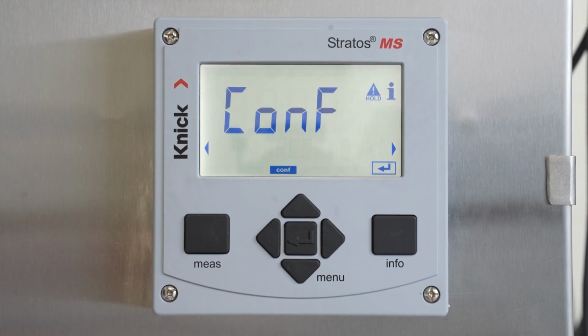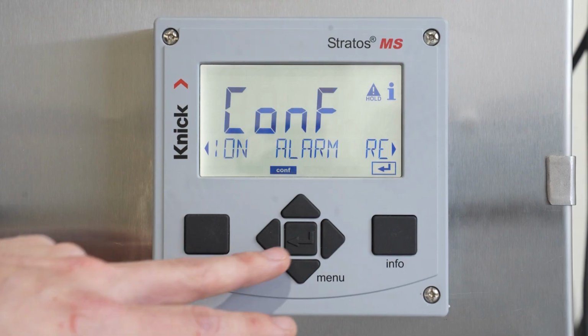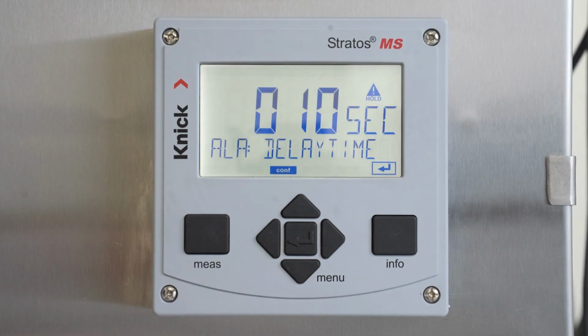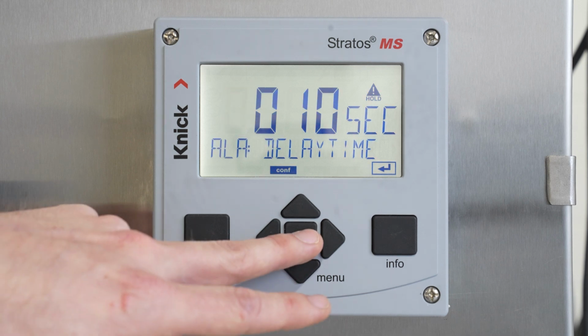Next, we have the option to set up a solution temperature correction. This feature is utilized when wanting to compensate online measured values to a known reference temperature. Moving on, we have the alarm setup. By pressing enter on alarm, you can see we can define our delay time before the transmitter goes into an alarm state. The default value for this is 10 seconds.